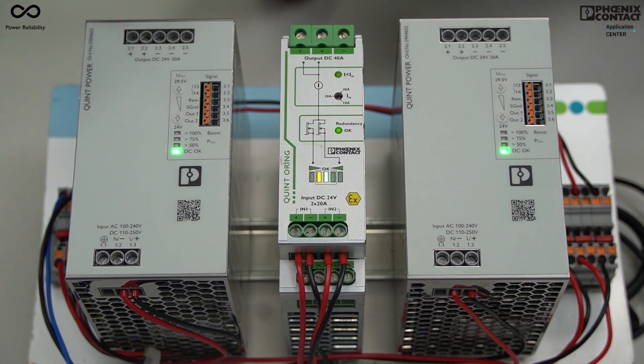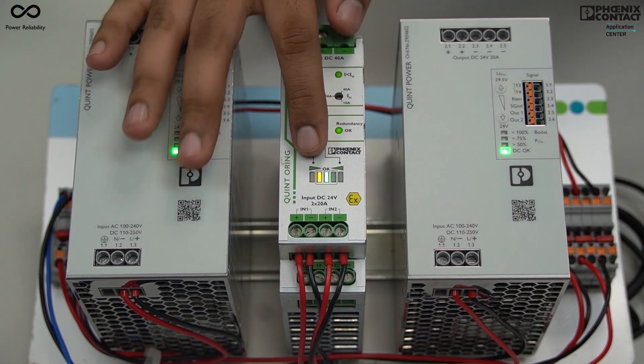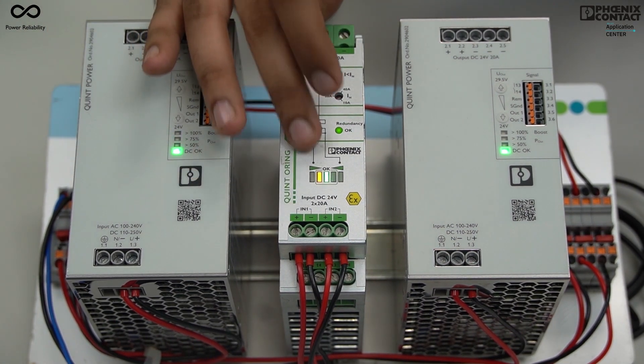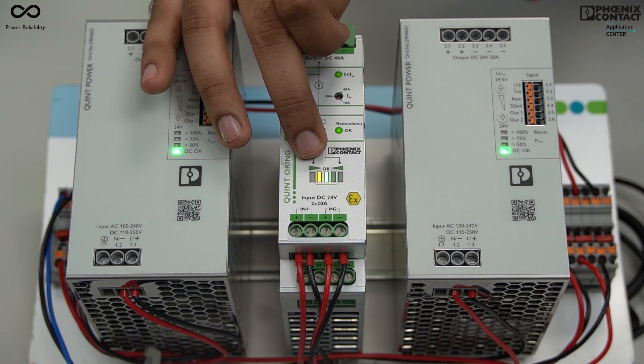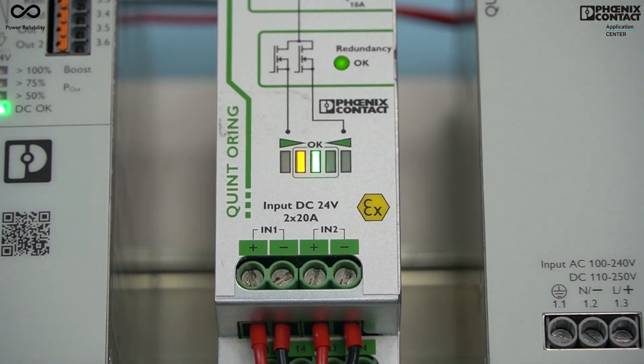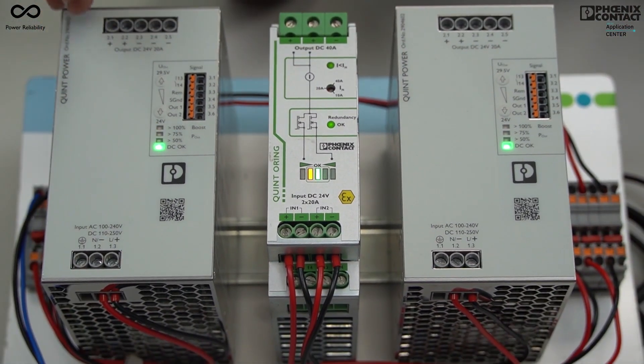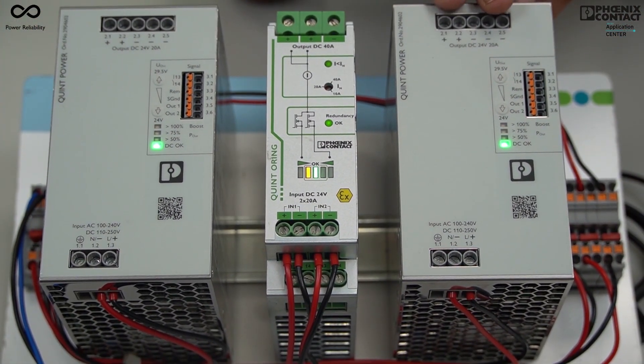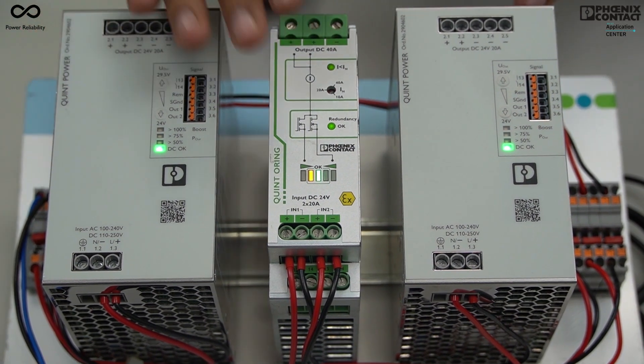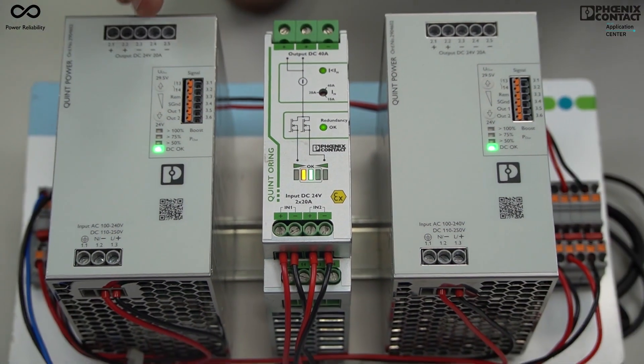I have changed the output voltage of the first power supply and you can see the indication in the yellow color. This shows that the first power supply is working at higher voltage and the second power supply is working at lower voltage. But this is still under control with auto current balancing feature.